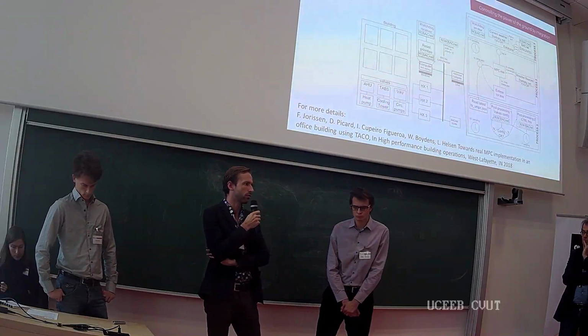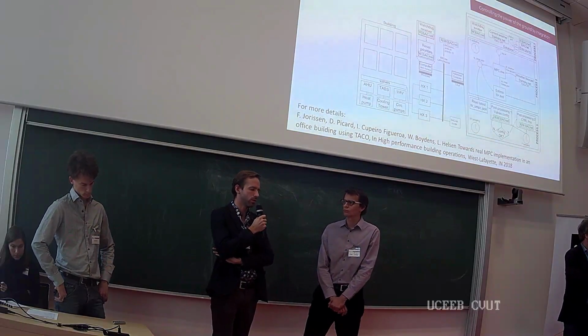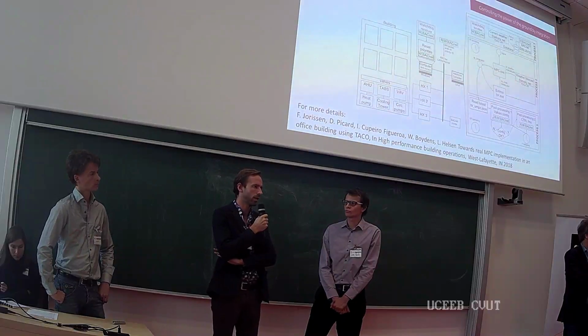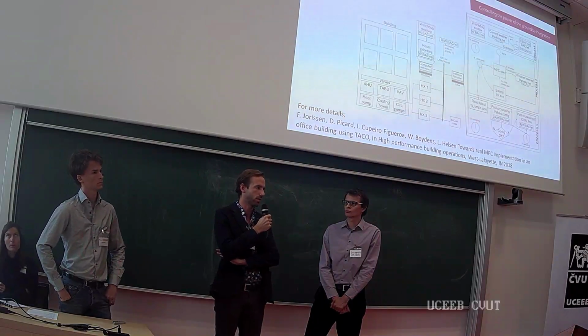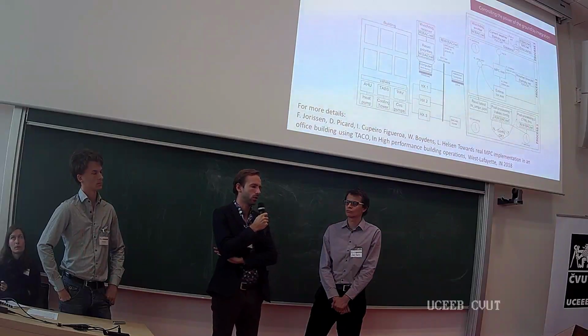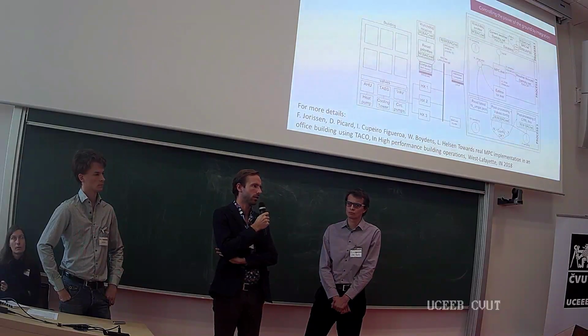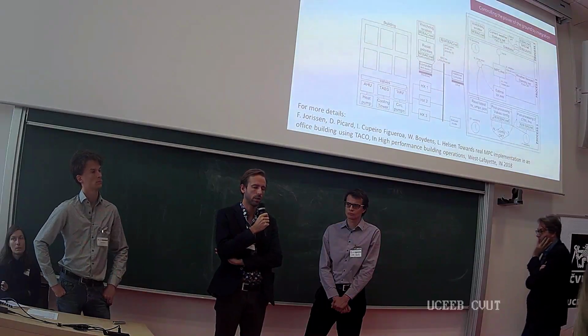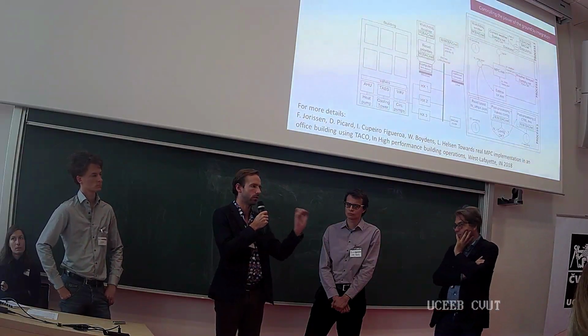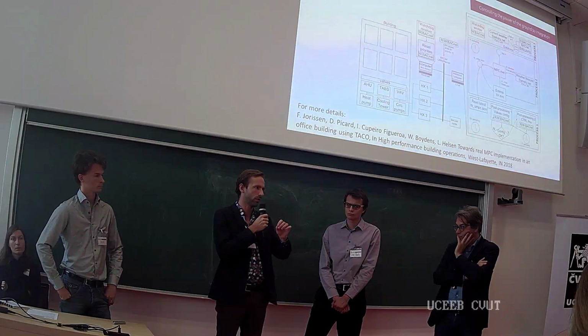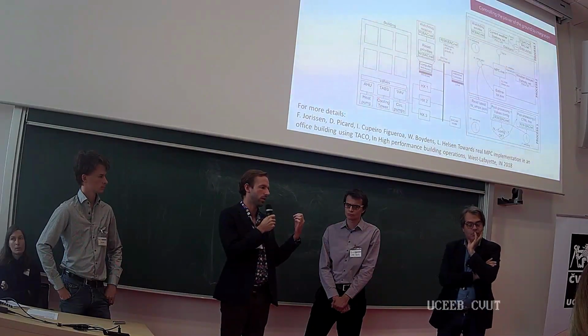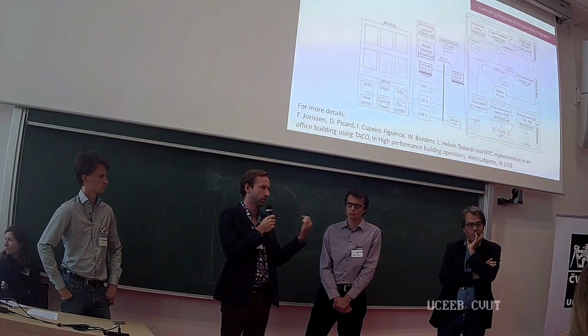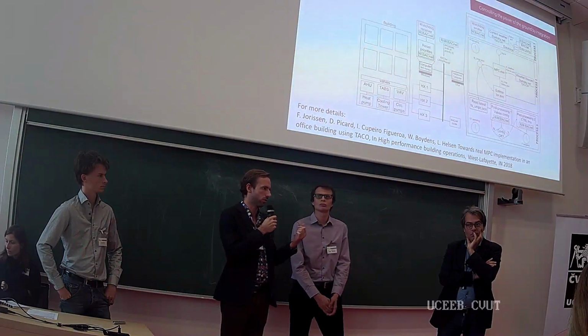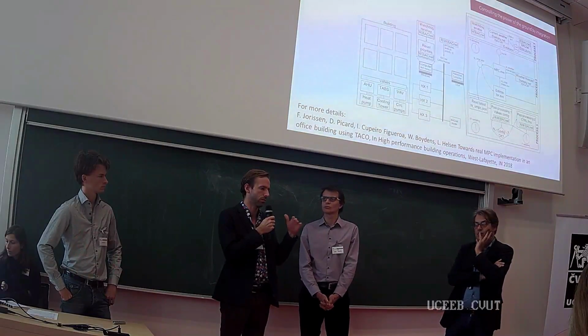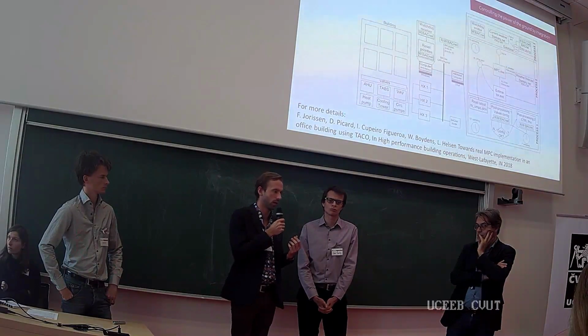That's something we partly still have to figure out based on experience, but our current approach is to put as much as possible into the MPC and switch to post-processing if we expect the MPC model isn't accurate enough. A concrete example: we directly control the two-way valve openings of the concrete core activation, but we don't expect to correctly predict the flow rate through it, simply because the valve characteristic isn't well known.